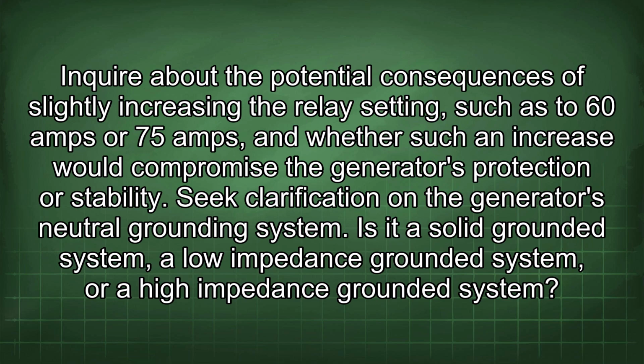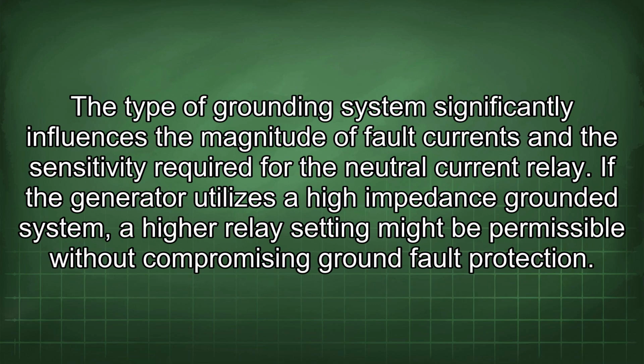Seek clarification on the generator's neutral grounding system. Is it a solid grounded system, a low impedance grounded system, or a high impedance grounded system? The type of grounding system significantly influences the magnitude of fault currents and the sensitivity required for the neutral current relay. If the generator utilizes a high impedance grounded system, a higher relay setting might be permissible without compromising ground fault protection.